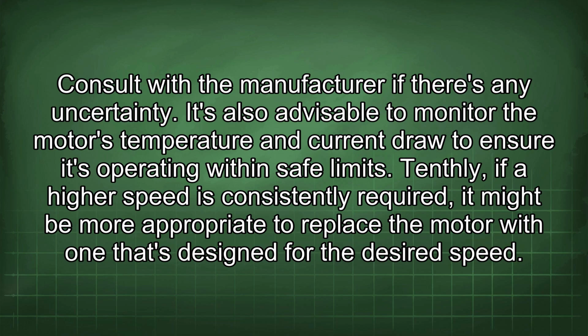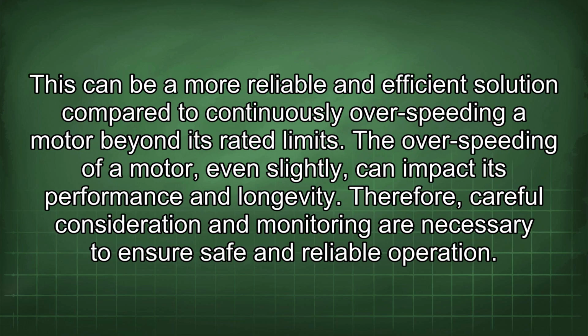Tenthly, if a higher speed is consistently required, it might be more appropriate to replace the motor with one that's designed for the desired speed. This can be a more reliable and efficient solution compared to continuously overspeeding a motor beyond its rated limits. The overspeeding of a motor, even slightly, can impact its performance and longevity. Therefore, careful consideration and monitoring are necessary to ensure safe and reliable operation.